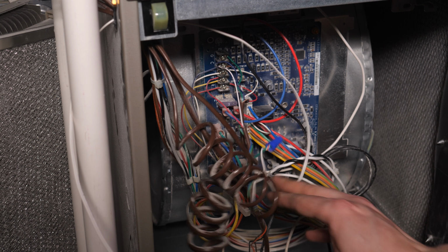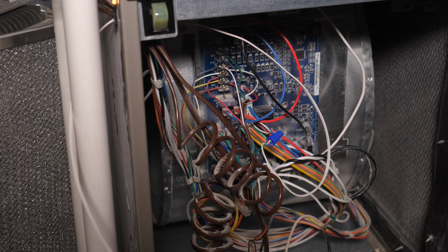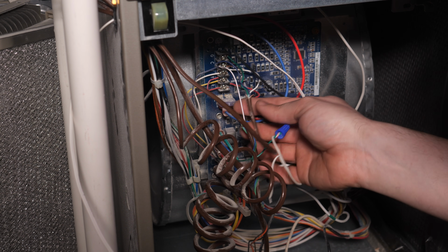If, though, my thermostat is commanding the heat to run, the humidistat is now aware of that, thanks to the fact that it's hooked up to the W terminal on the furnace board. So, as before, if the humidity is below the set point, it will close the relay and send power to the humidifier. And once it's satisfied, it shuts the humidifier off.